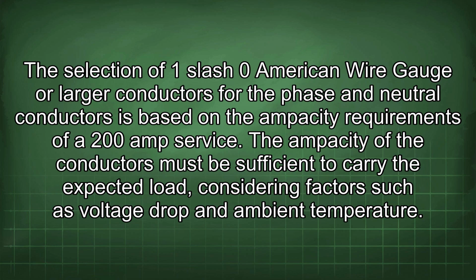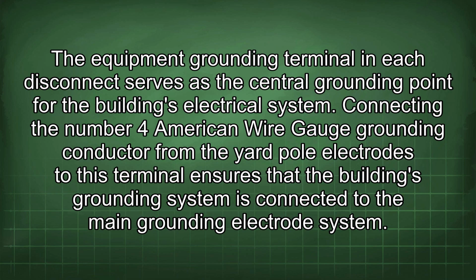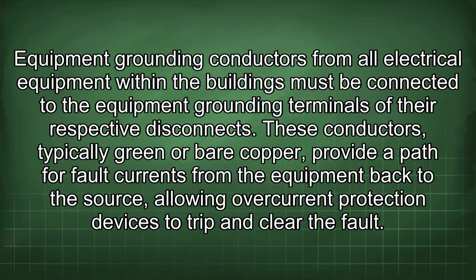The equipment grounding terminal in each disconnect serves as the central grounding point for the building's electrical system. Connecting the number 4 American wire gauge grounding conductor from the yard pole electrodes to this terminal ensures that the building's grounding system is connected to the main grounding electrode system. Equipment grounding conductors from all electrical equipment within the buildings must be connected to the equipment grounding terminals of their respective disconnects. These conductors, typically green or bare copper, provide a path for fault currents from the equipment back to the source, allowing overcurrent protection devices to trip and clear the faults.